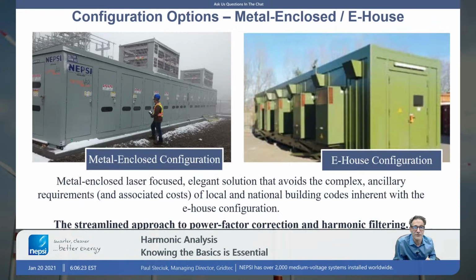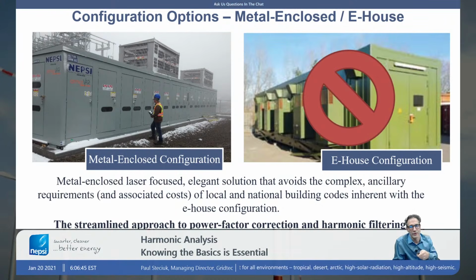There's E-house configurations, the one on the right. It looks like a metal-enclosed solution, but it's a lot different. The E-house configuration is a walk-in type cubicle. You walk in there, you can grab components, and everything is pushed into that enclosure. That enclosure must be designed and built according to the local building code standards. And again, we do not build that type of equipment. We only build metal-enclosed.